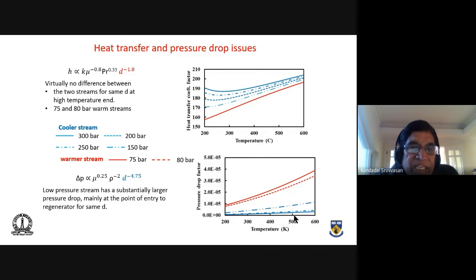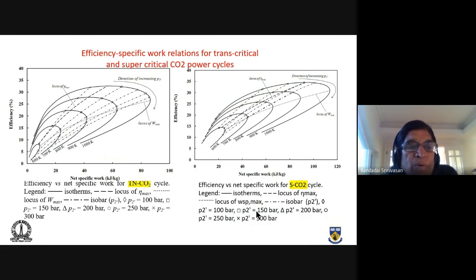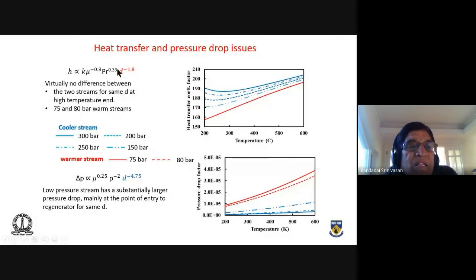The reason for that is that in the turbulent region, the heat transfer coefficient is proportional to the velocity or mass flow rate to the power 0.8, because that is Re power 0.8, and Prandtl number roughly about 1/3 you will get. Prandtl number in this case is the same, whether it is carbon dioxide cool, it doesn't change much, it changes a little bit. Prandtl number is locked in because of the properties of the fluid. It's about 1/3 here. Now, if you take Nusselt number and other correlations into account, the heat transfer coefficient is proportional to diameter power minus 1.8 and Prandtl number. That's after taking into account the mass flow rate.